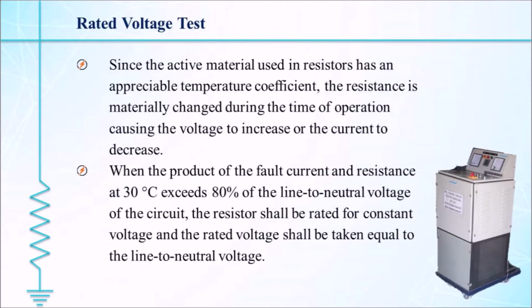Rated voltage test. In this test, rated voltage is given to the NGR by an external source. This voltage is kept for 1 minute. If the voltage is sustained across the terminals and resistance, then this test is successfully performed.